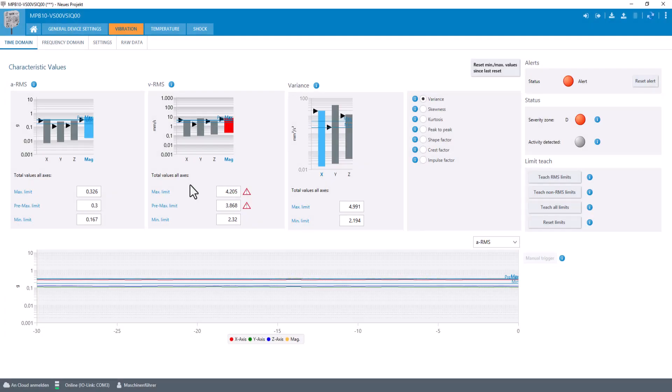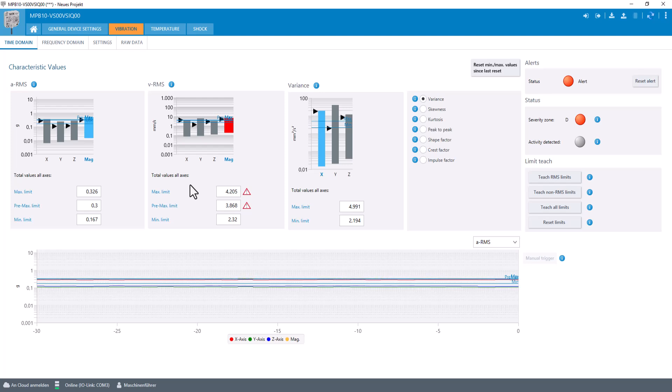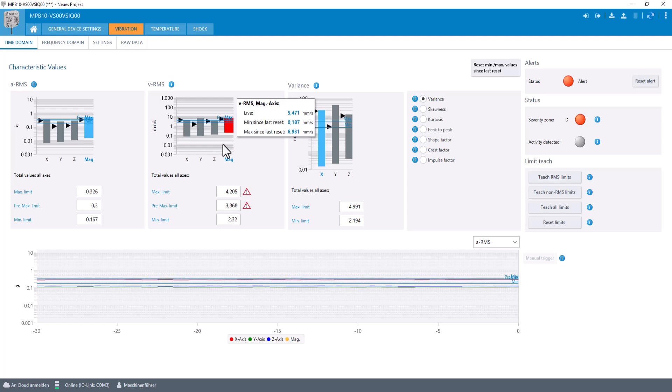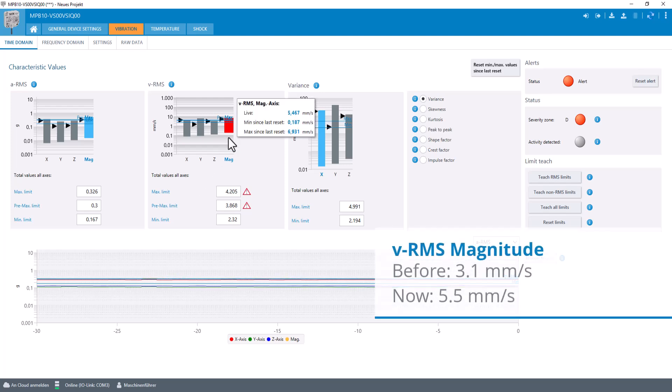By looking at the time domain values, we can instantly see the difference in the energy contained in the vibration. The values increased, especially the VRMS magnitude is way higher than before.